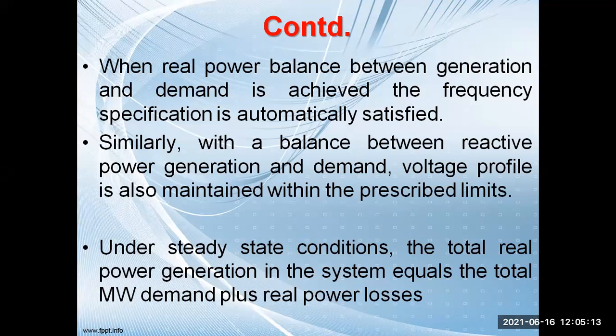Similarly, with a balance between reactive power generation and demand, the voltage profile is also maintained within the prescribed limits. We have to understand two things. If there is a balance between the active power generation and the active power demand, the system frequency will be maintained. Similarly, if there is a balance between the reactive power generation and the reactive power demand, the voltage profile will also be maintained. Under steady state condition, the total real power generation in the system equals the total megawatt demand plus the real power losses.